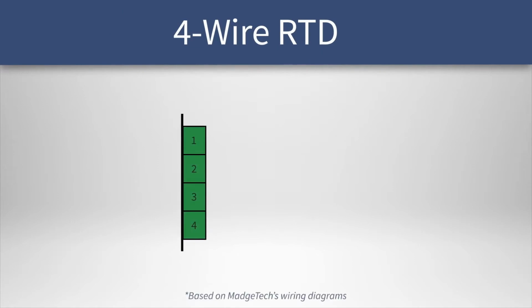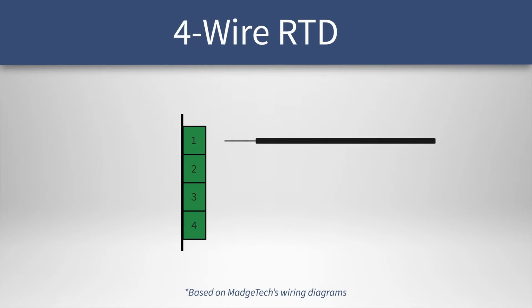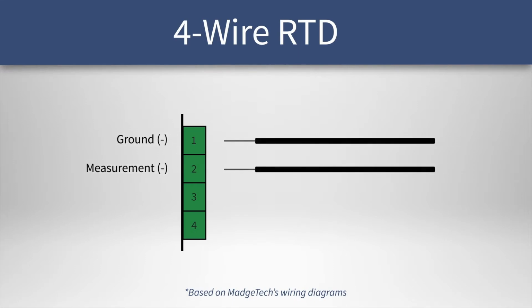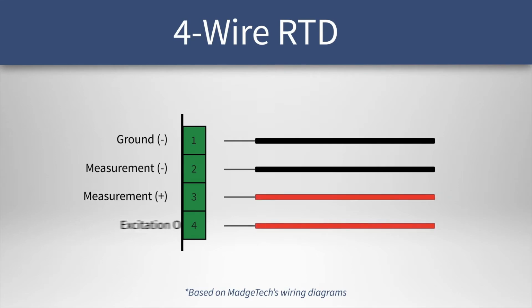Our first example is a 4-wire RTD probe, which is in most cases the best choice when available. According to MadgeTech's wiring diagram, a black wire should be connected to terminal 1, and in terminal 2, another black wire. A red wire should be connected to terminal 3, and then the other red wire should be connected to terminal 4.